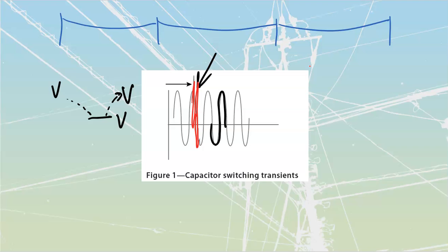The other thing that happens with capacitor banks is when they switch them on. If my voltage is supposed to be at a certain level but it's sagging away, an automatic capacitor is supposed to bring it back up by correcting the lagging power factor, but it takes a bit before the transformer voltage regulators respond by changing the taps.